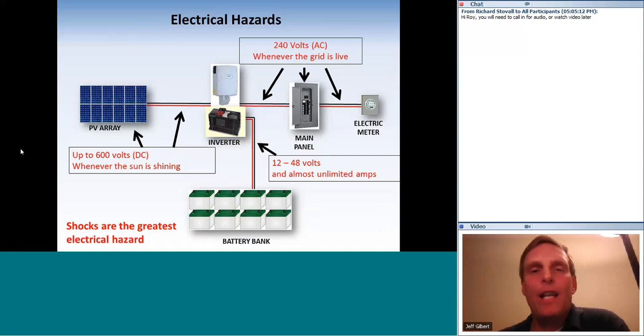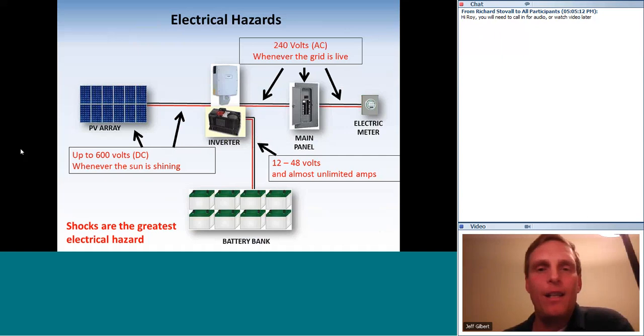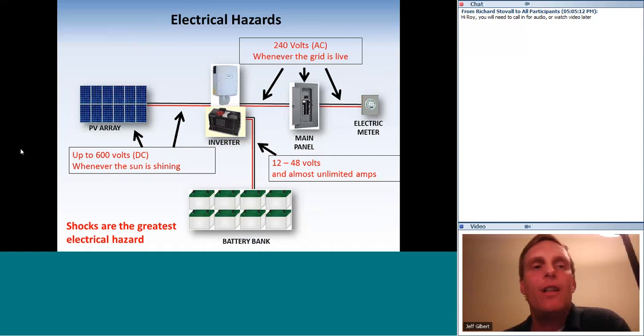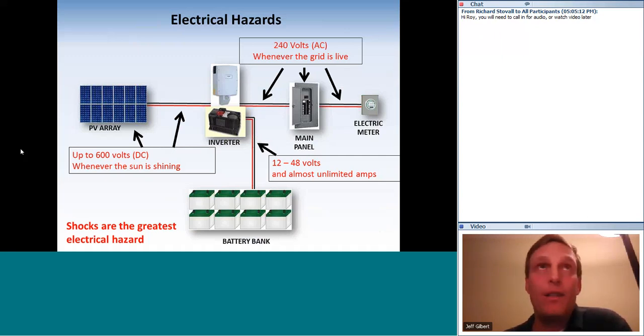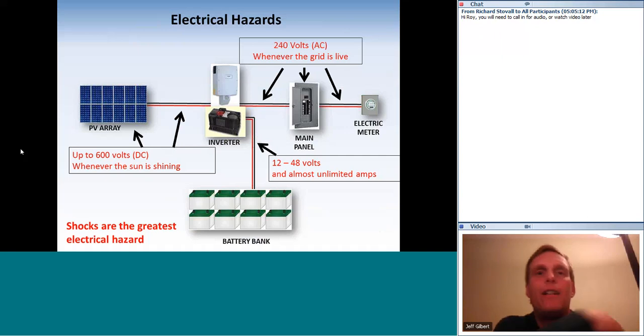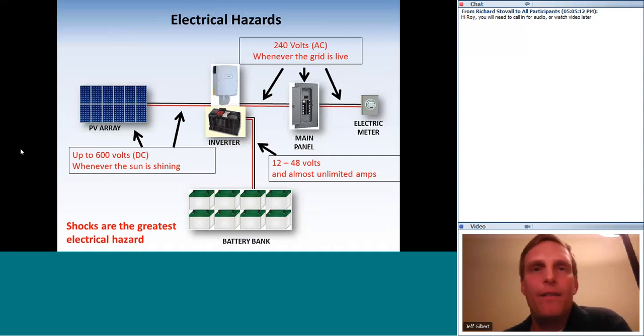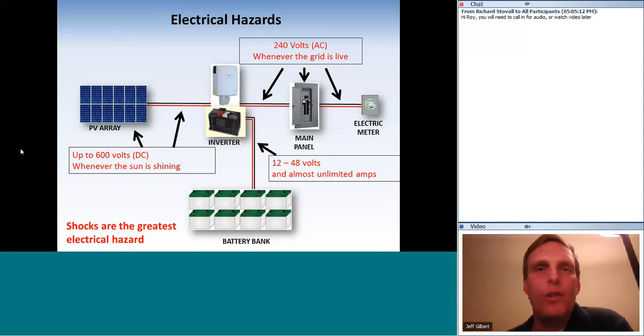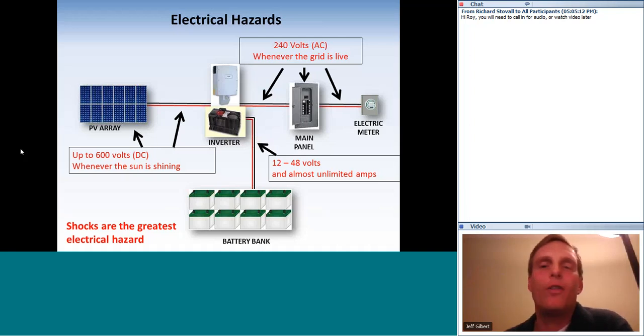On the DC side of a typical solar energy system, voltages can reach up to 600 volts for residential applications, and up to 1200 volts for large industrial or megawatt-scale projects. On the AC side, residential applications in the U.S. run at 240 volts; overseas it's typically 220. Commercial applications may see 208, 277, or 240 volts. They're all dangerous.